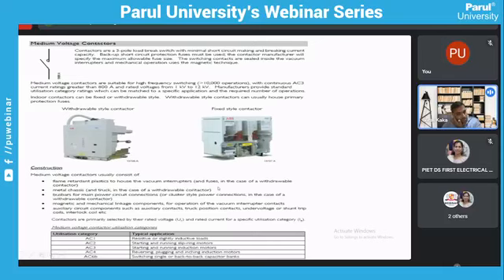Coming to the next point, this is another variant which we normally offer in medium voltage switchgear. This is a medium voltage contactor. Now contactors are predominantly used in DOL type starters and for motor applications. The design of this sort of contactor comes in withdrawable style as well as fixed. If it is a fixed style contactor, the fuses will be external, connected from the top copper jumpers. But if it is a withdrawable type of contactor, the design has the fuses as part of the contactor assembly. That is an inherent design of how vacuum contactors are developed.